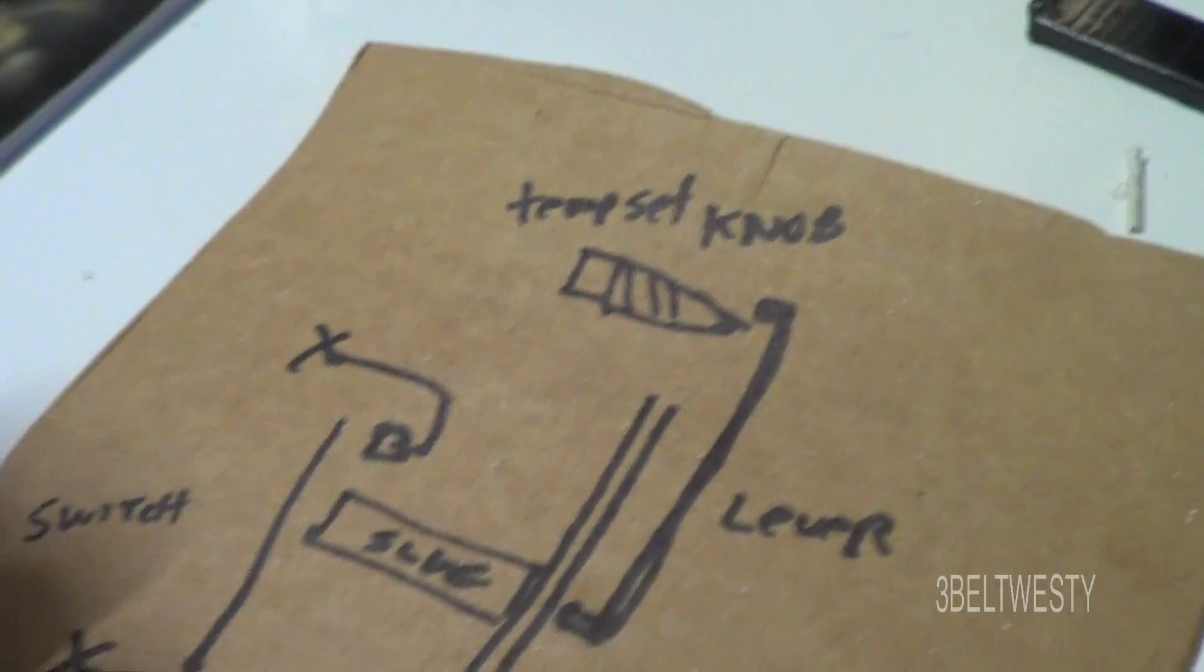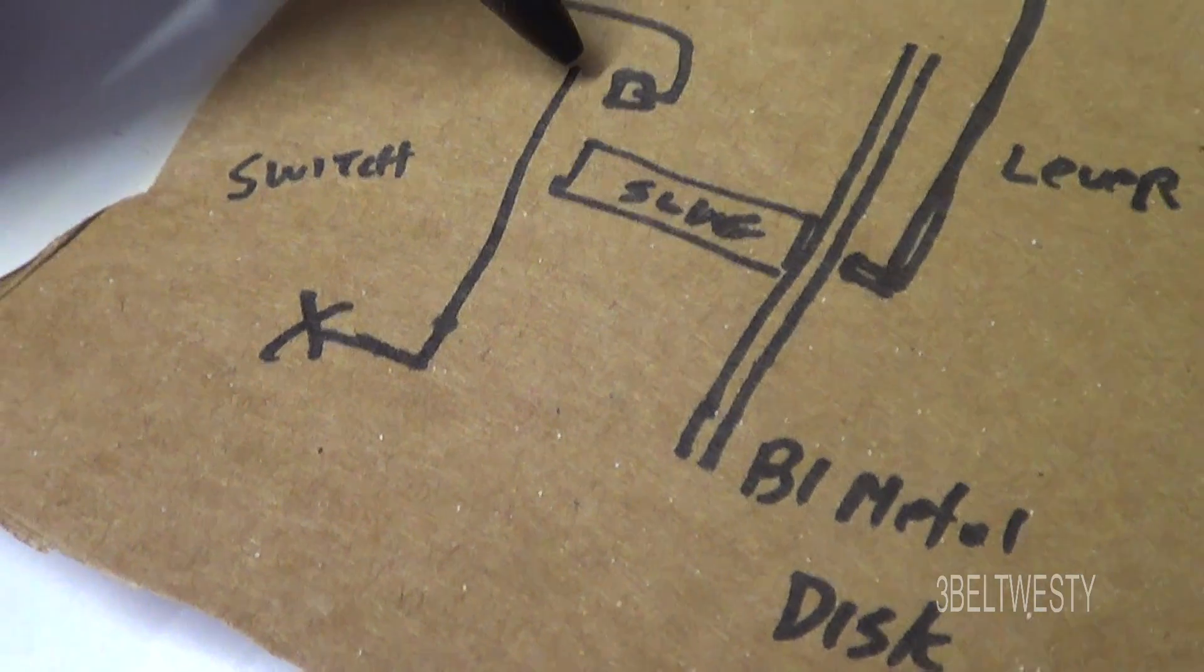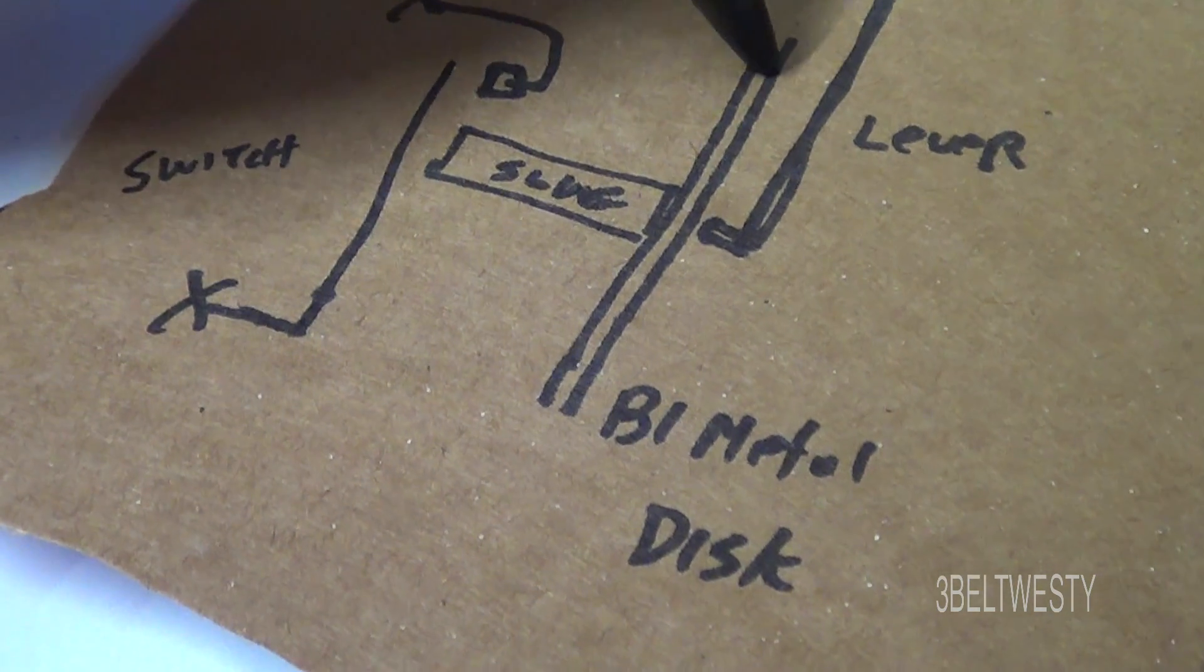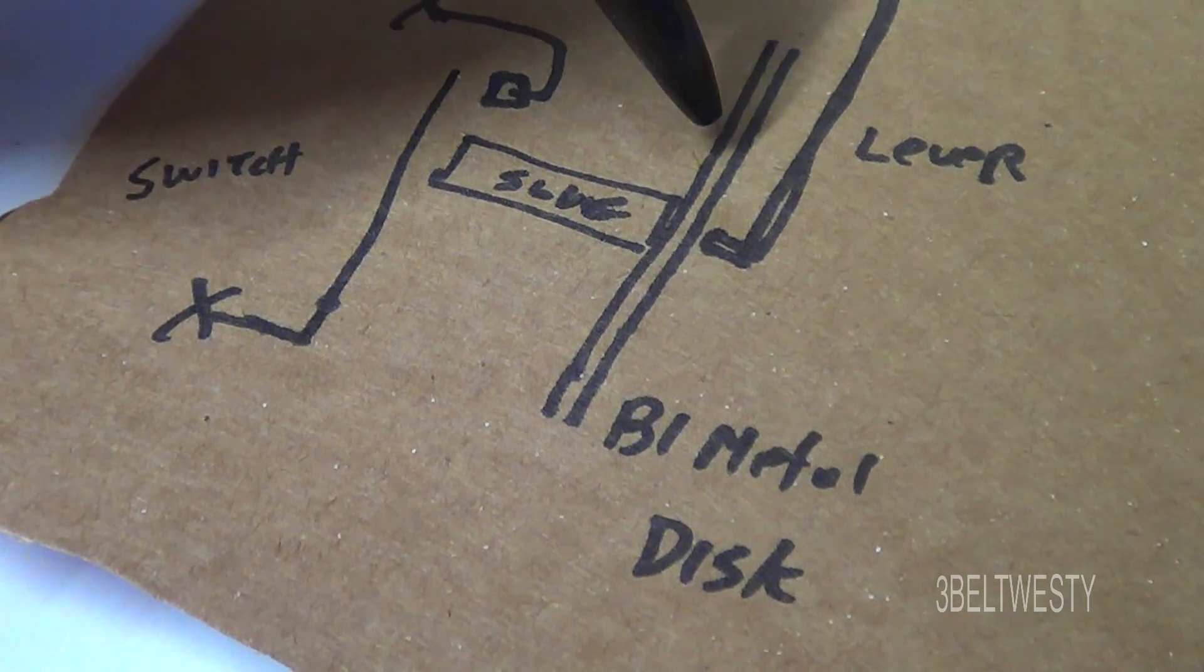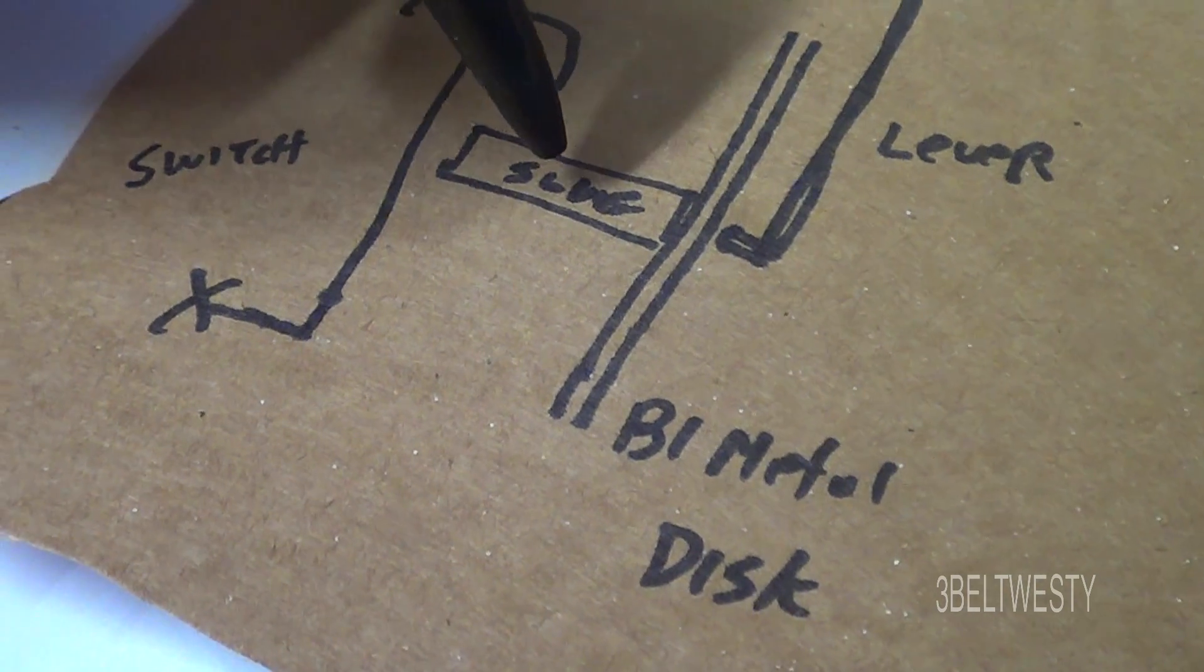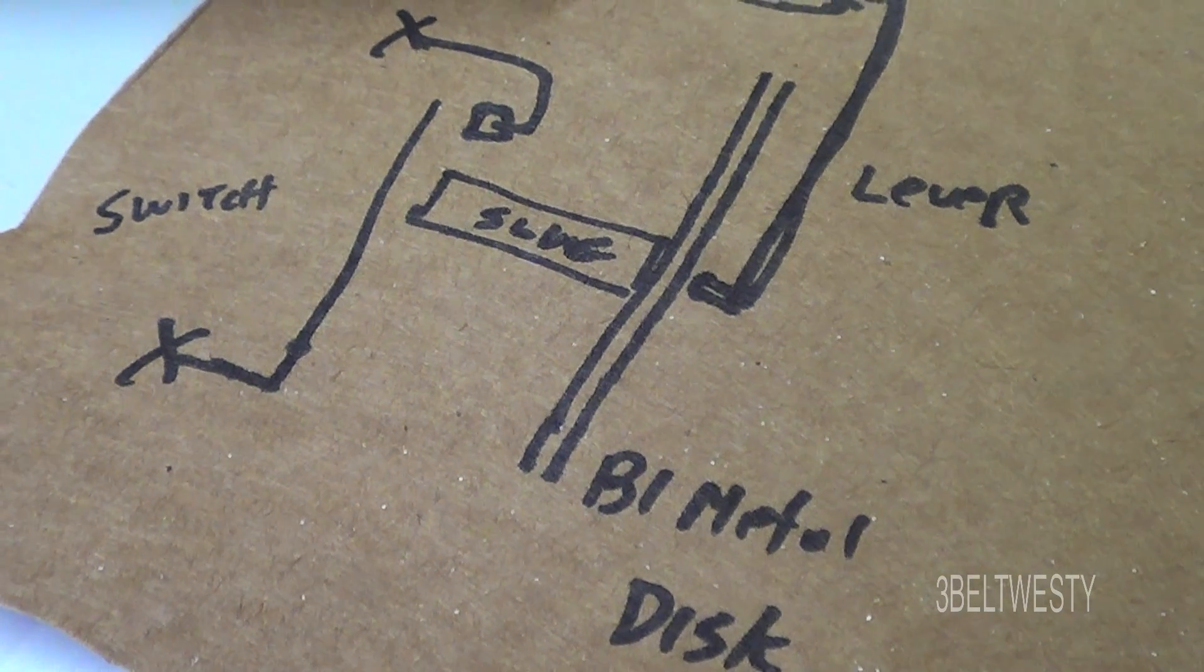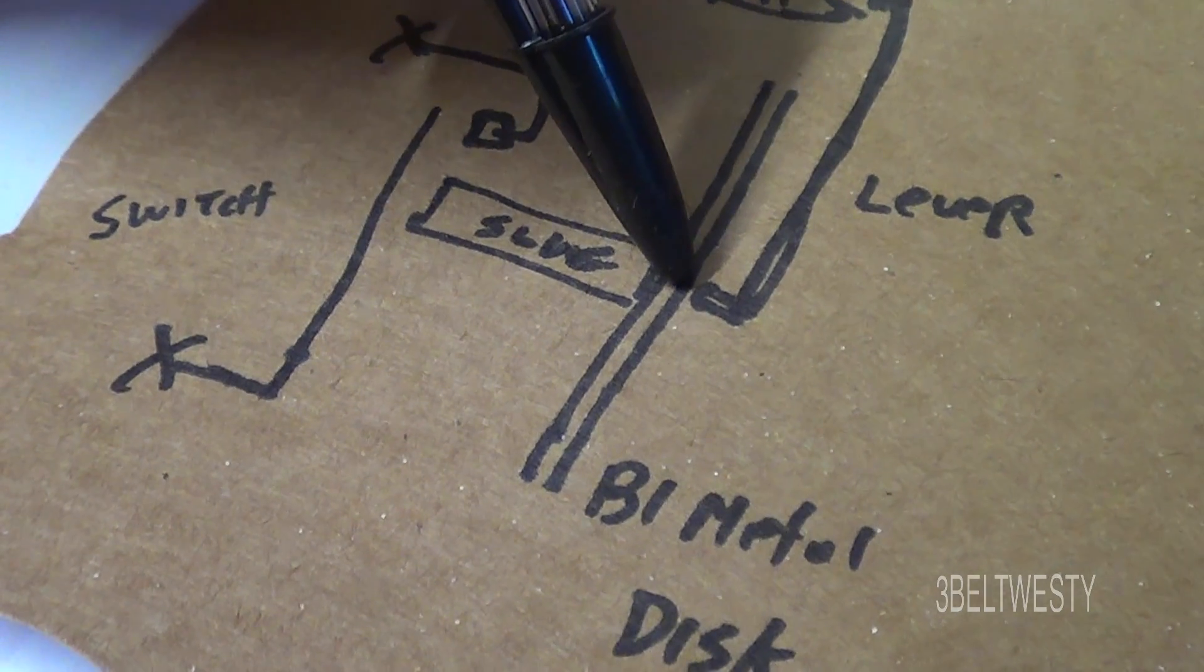Here's a diagram. You've got the switch. Here's the switch contact right here that goes back and forth. Here's this movable slug. And here's this bimetallic disc with the two sides of the material. So when it gets hot, it goes through and moves back and forth. The slug should move back and forth to turn the switch on and off.